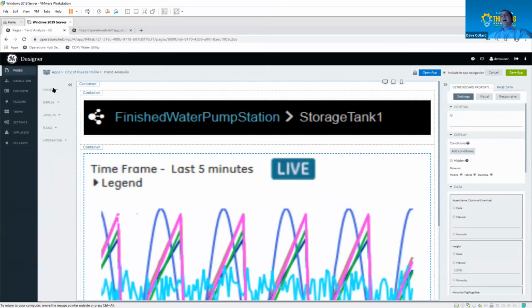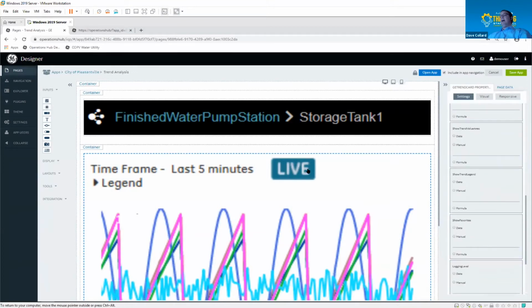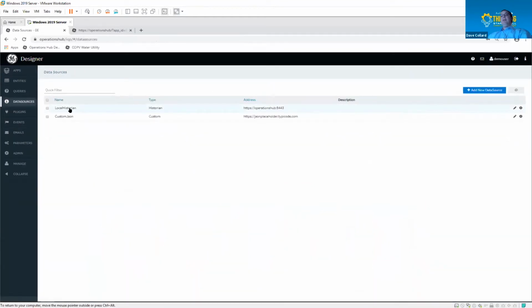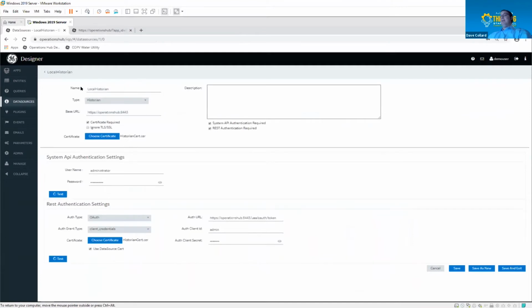Other widgets would have the ability to say, am I connecting to a REST API, a relational database connection, albeit our historian again, in the future, at the end of this calendar year, OPC UA and our HMIs. And that all gets configured by this right-hand pane here, which has all the properties of the object for configuration. And when it asks you what type of object is it that you're going to connect to, that all gets defined in the higher level app area called data sources. And quite simply, we just say, here's our historian, and we specify the name of it.